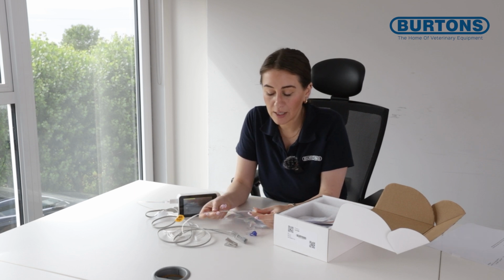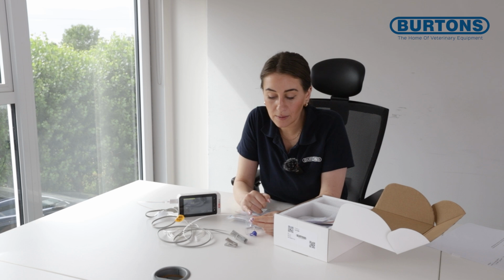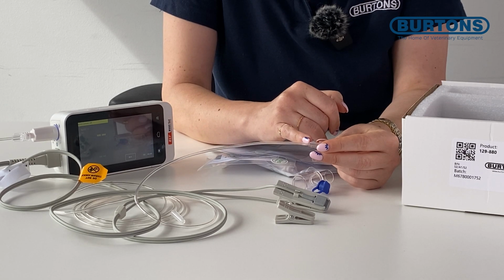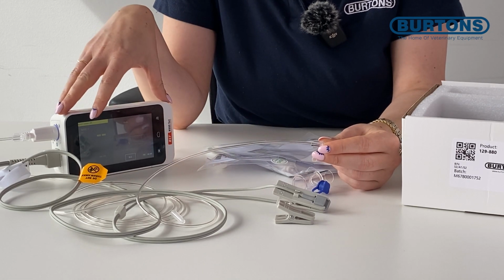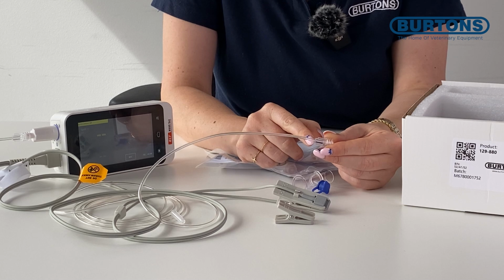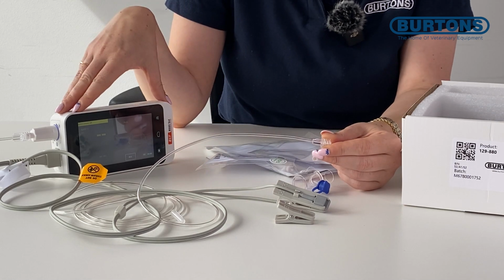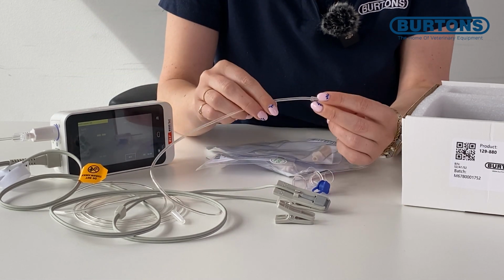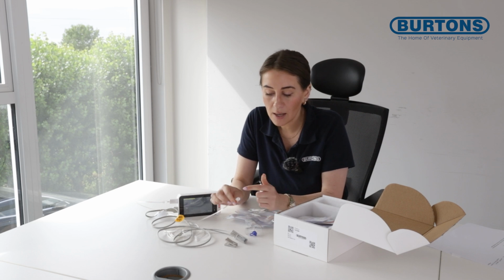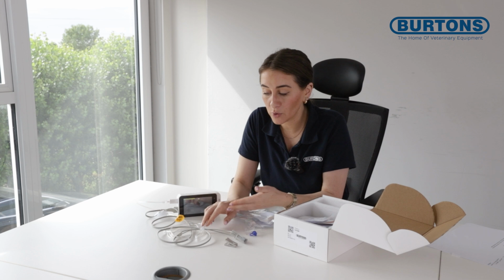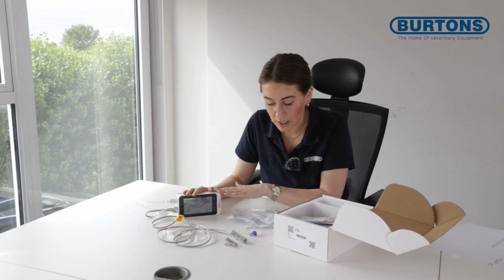The sample tubes, these need to be replaced as and when. Most often they either become blocked, so we're not getting a CO2 reading, or a crack forms and we start getting really low end tidal CO2. So it's really important to have a number of these on site. A lot of the time they can get stepped on and cracks will form, so if you don't have an adequate sample tube, you won't be able to use the capnography portion of the machine.